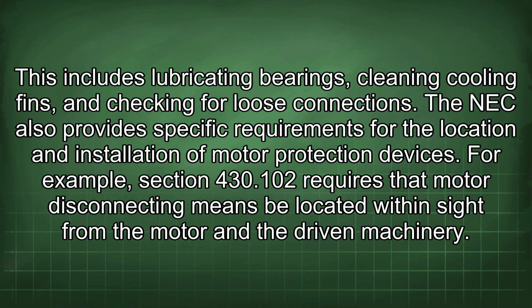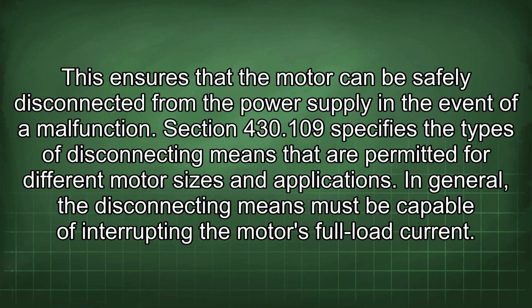The NEC also provides specific requirements for the location and installation of motor protection devices. For example, Section 430.102 requires that motor disconnecting means be located within sight from the motor and the driven machinery. This ensures that the motor can be safely disconnected from the power supply in the event of a malfunction. Section 430.109 specifies the types of disconnecting means that are permitted for different motor sizes and applications. In general, the disconnecting means must be capable of interrupting the motor's full load current.